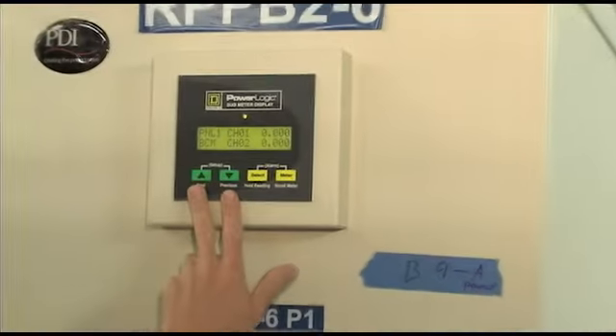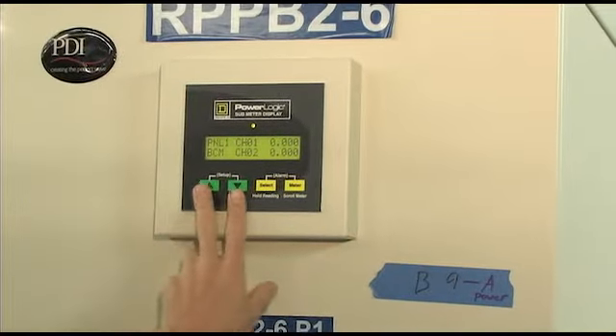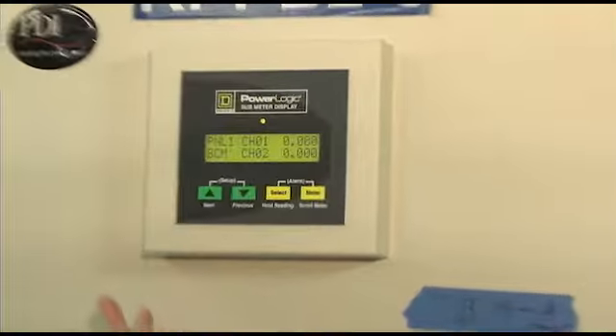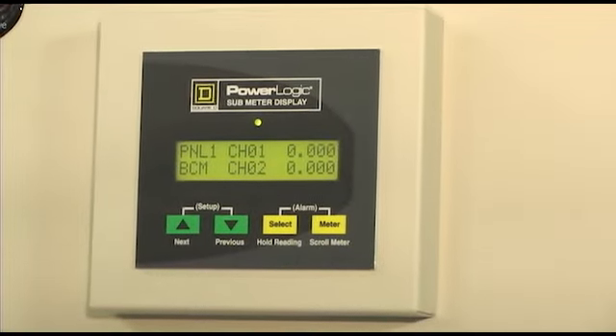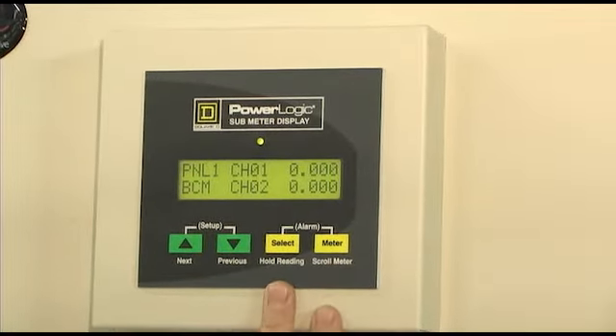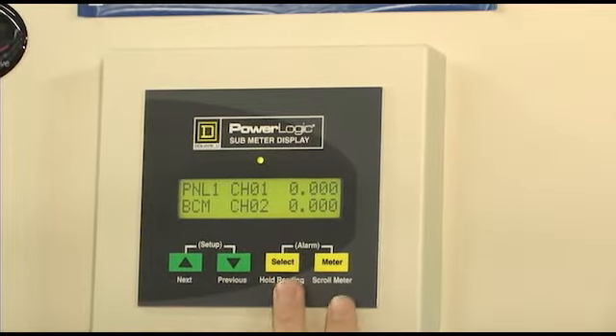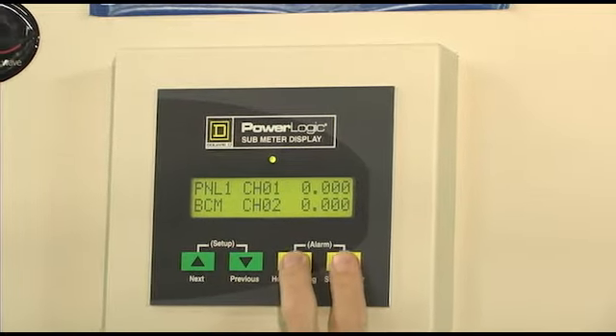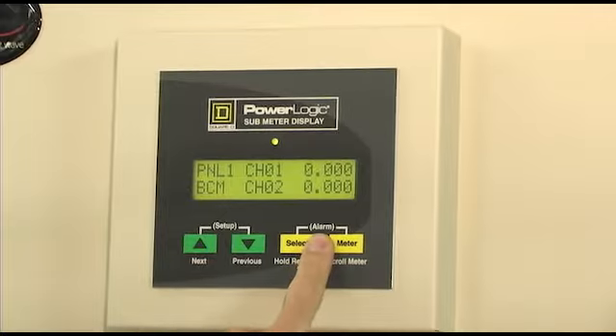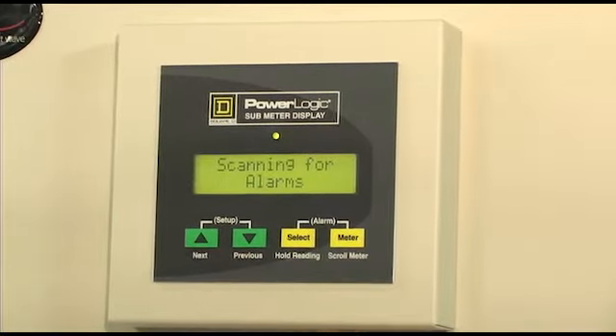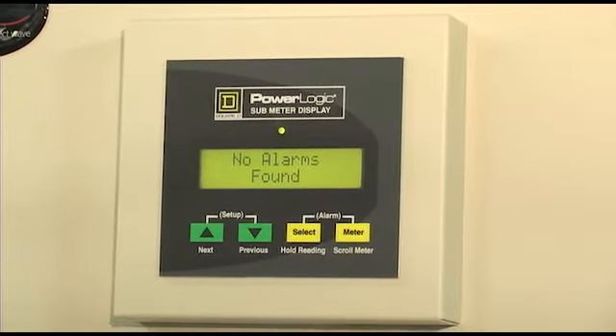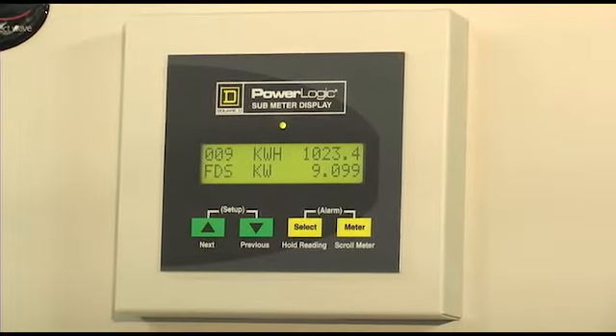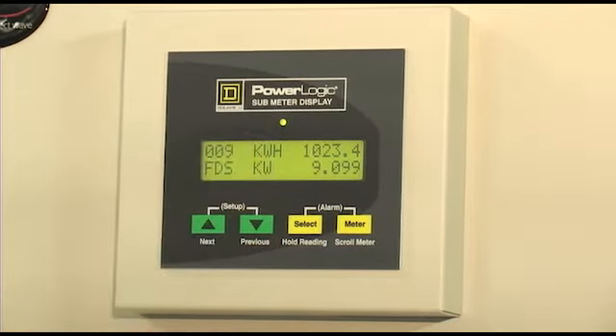Basically right here when you press these two buttons, as it indicates it's set up, and you can go in there for certain reasons that most people won't need to go into. The main thing is checking out your metering. If you want to check the alarm record to see if there's any alarms, you just press both of these, which indicates right here, press both for alarm. It scans for alarms. It found no alarms. When you approach this machine, you'll see that the light may not be green, which means it is already an alarm.